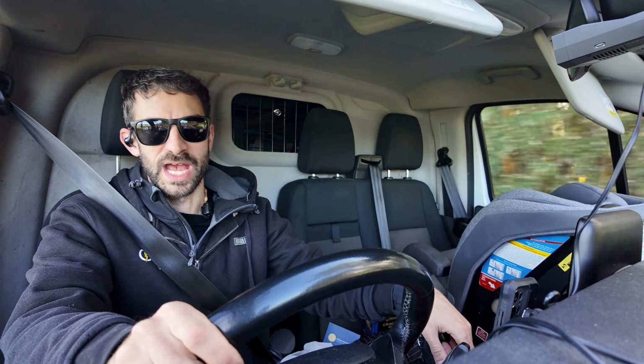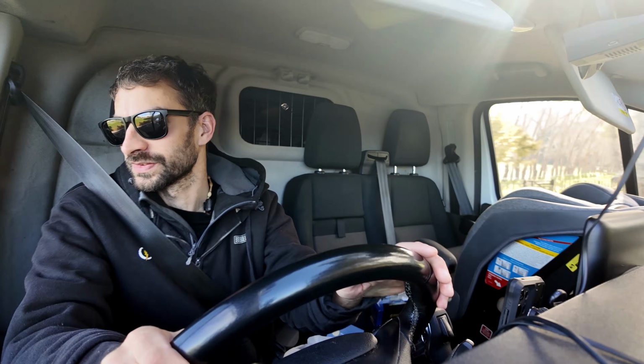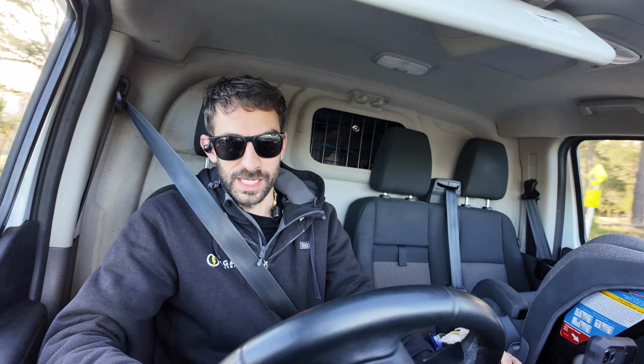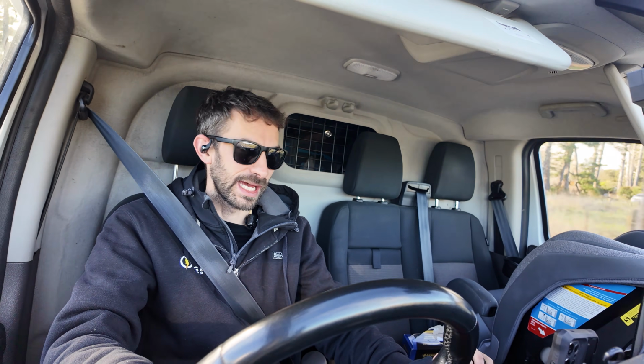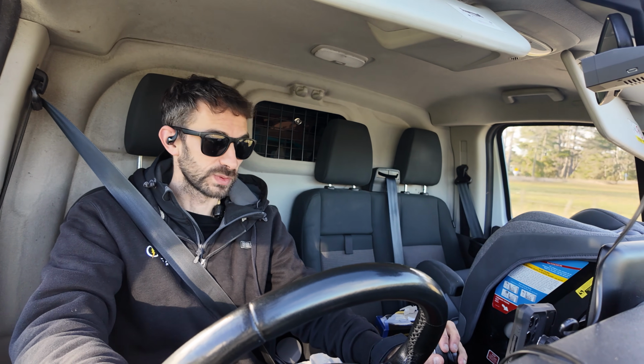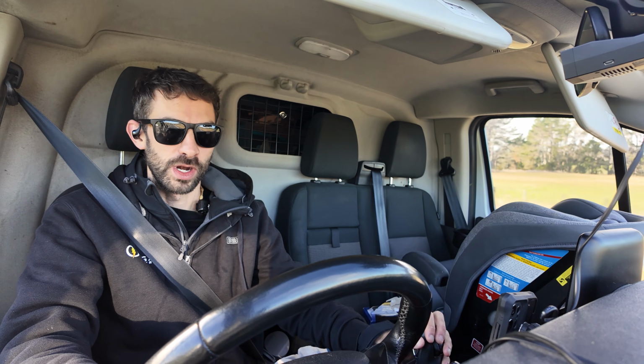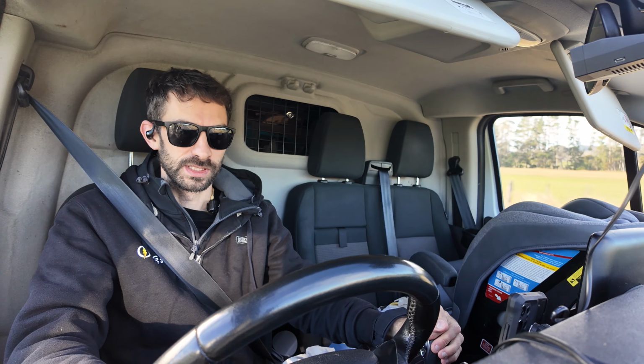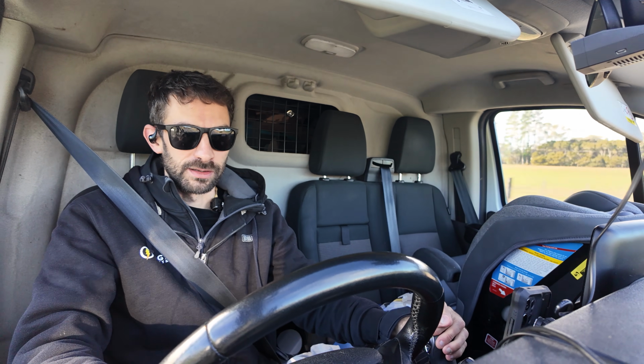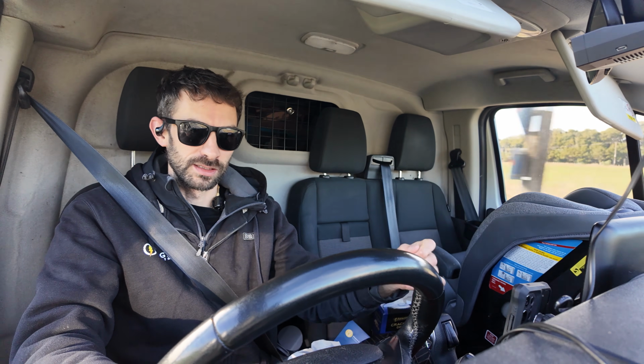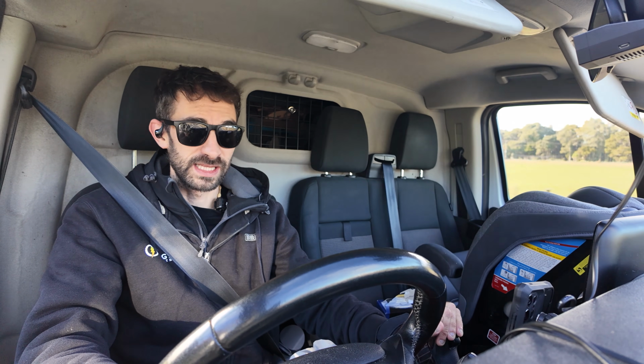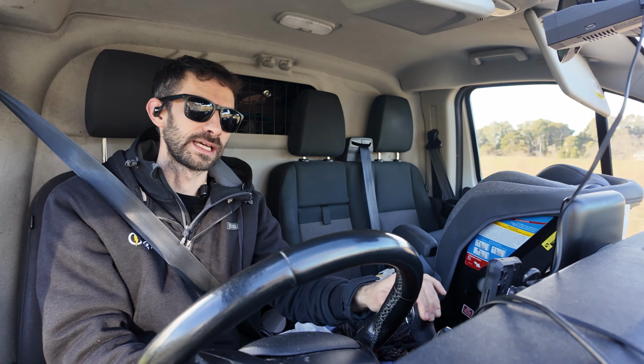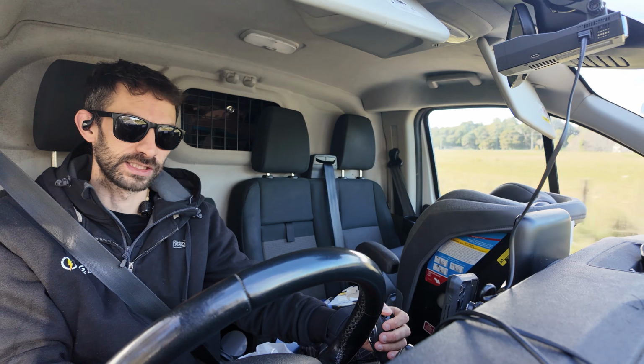A lot of electricians usually get shocks from time to time throughout the course of their career. Shouldn't be, but it happens. But usually nothing happens because we're wearing boots, we're standing on an insulated ladder, we're not holding the other side of the metal cabinet. When we get the shock, you just get a little tingle. But if you're really well earthed and you come in contact with that same conductor, the results could be catastrophic.